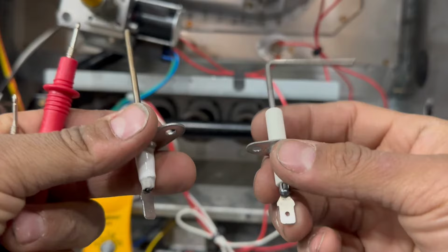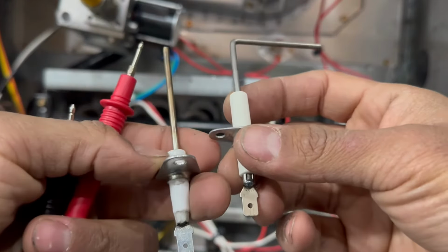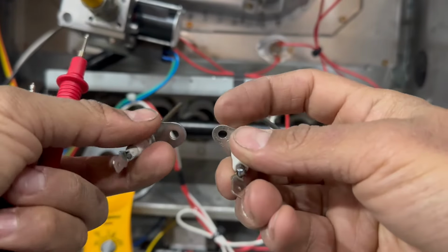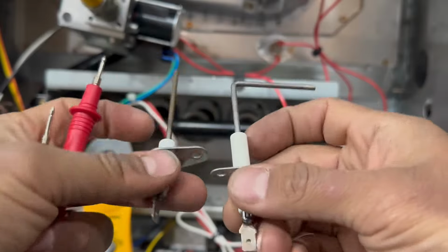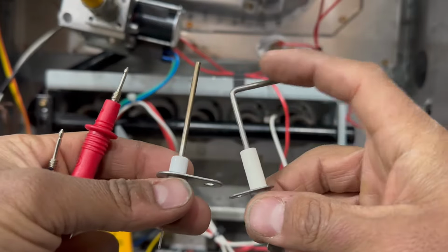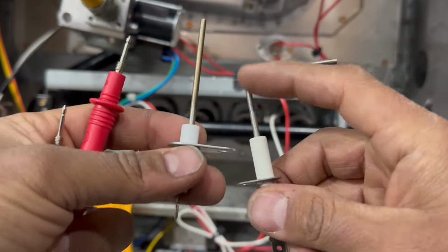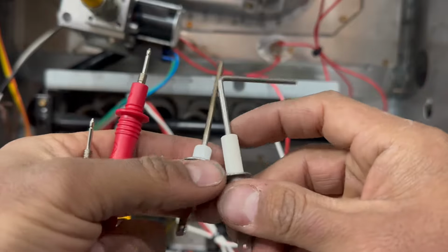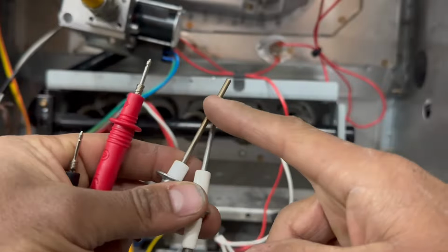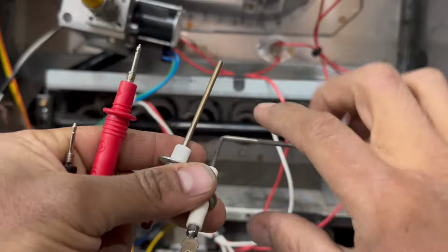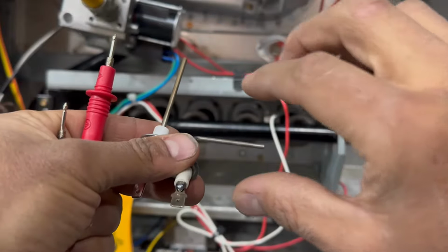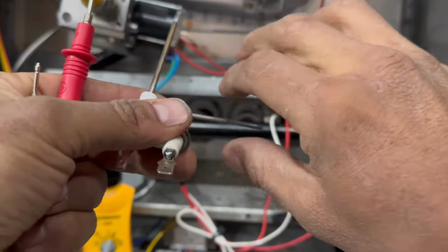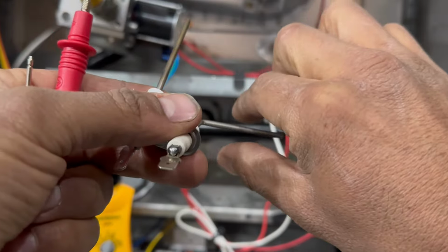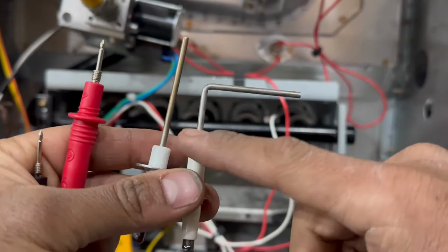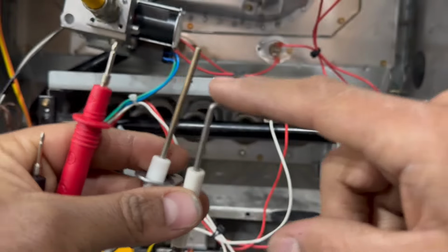For different furnaces, this one here, they're the same. You have a wire connected to it. You've got a little screw you have to take out or put in, and then you just have the piece of rod, right? That flame sensor. So basically, this top part is what gets dirty. This is what's getting that flame. That flame is hitting it full on all the time when the heating is on. So a lot of the times these get dirty.